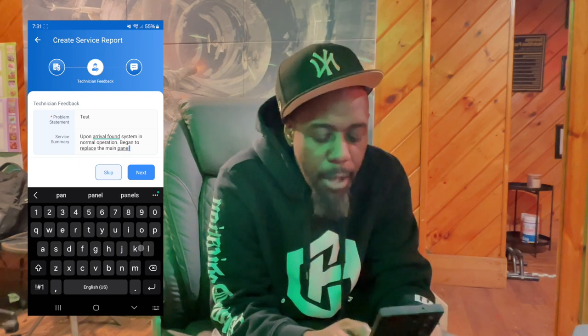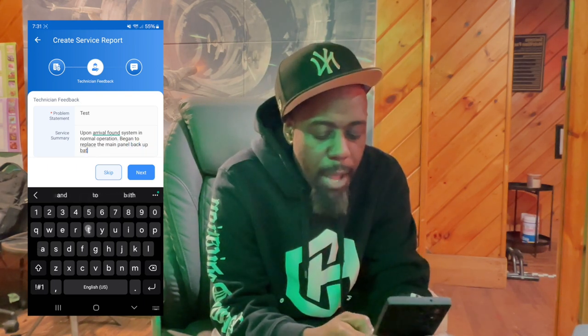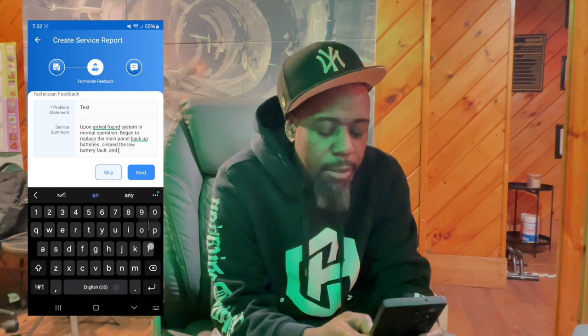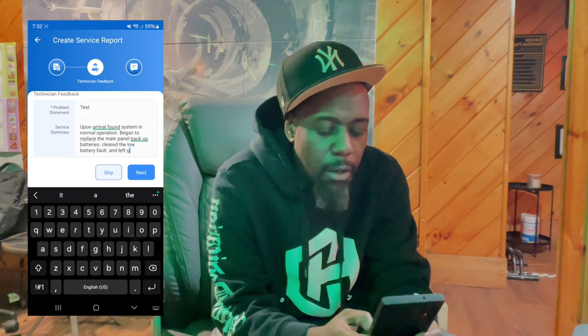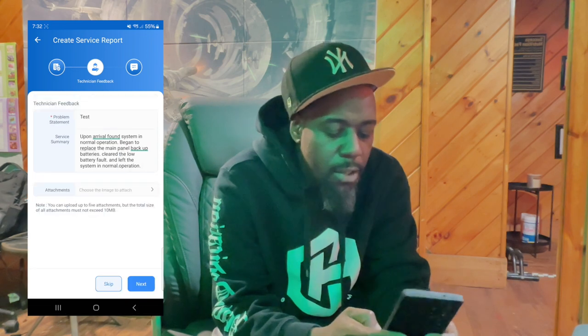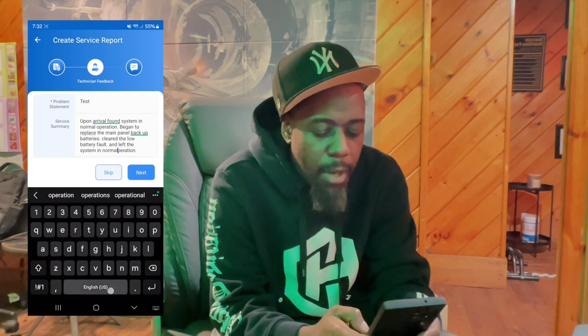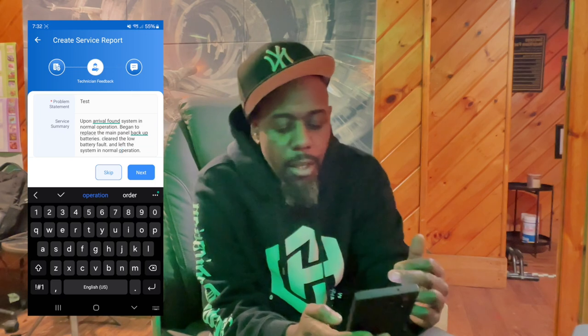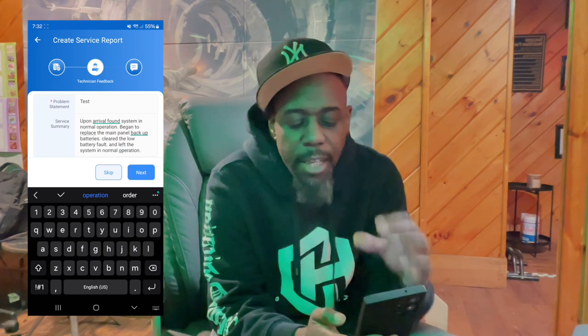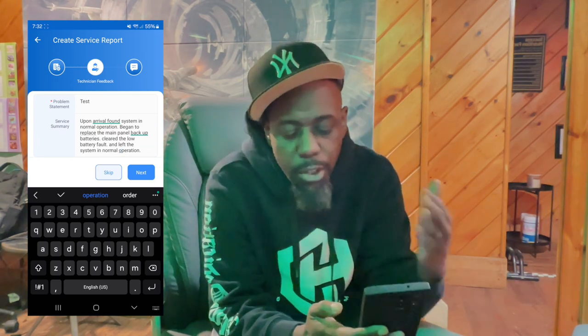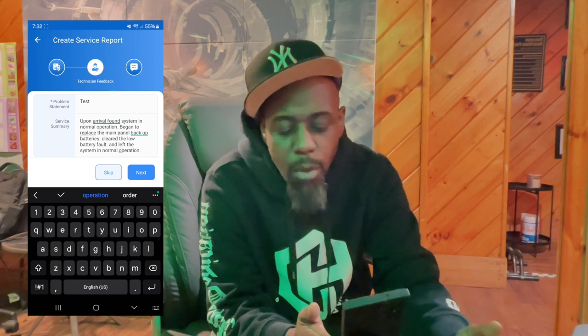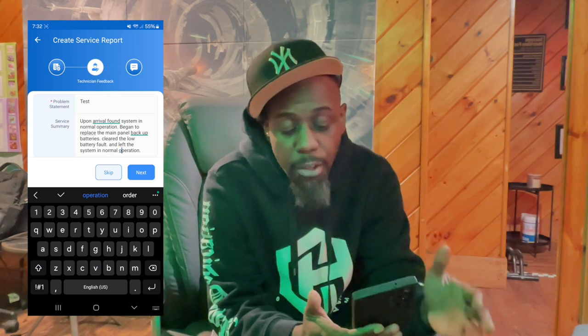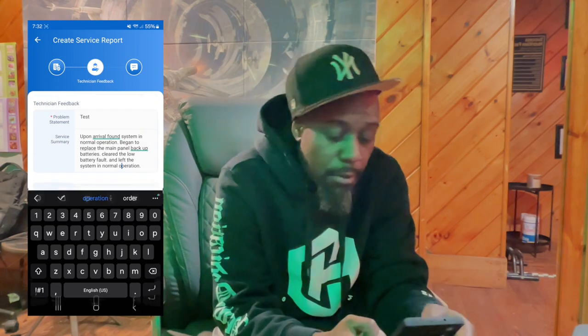State exactly what you replaced — for example, 'Replaced the main panel backup batteries, cleared the low battery fault, and left the system in normal operation.' This is how the service ticket should look. I don't really care about complete sentences — you can even list it — but you have to put detailed information in there: what you found when you got there, what you did, and how the system was after you left.